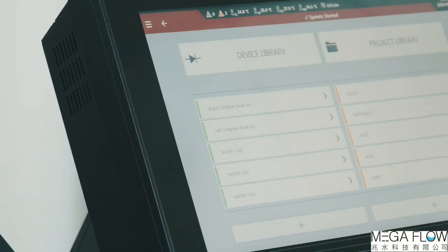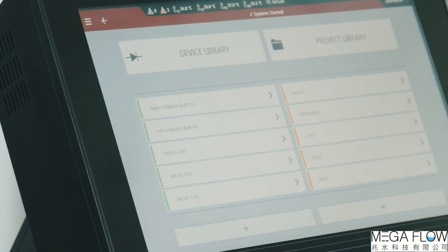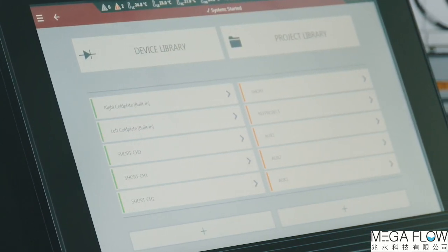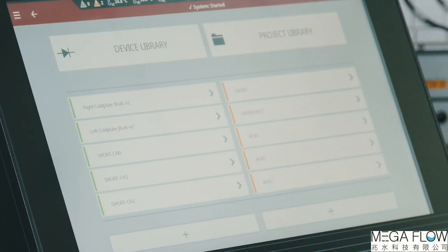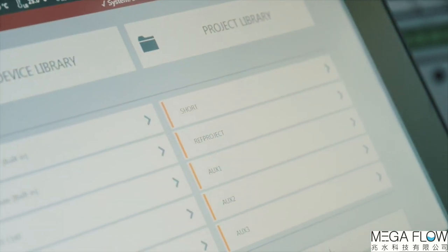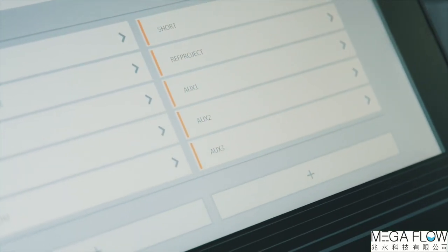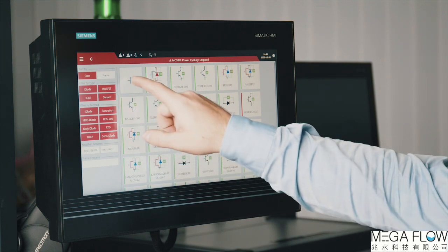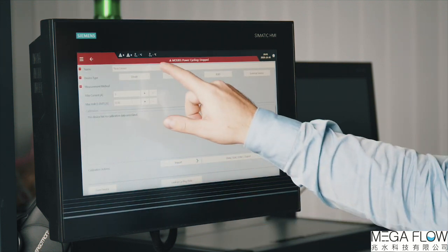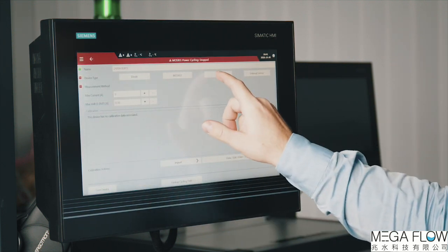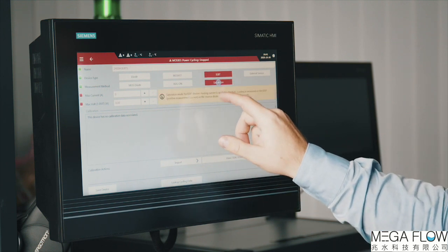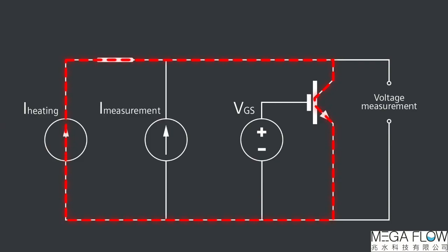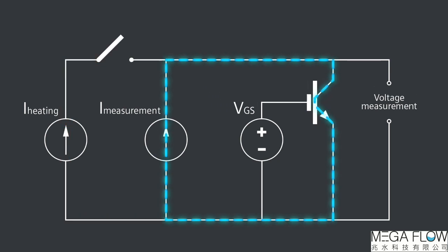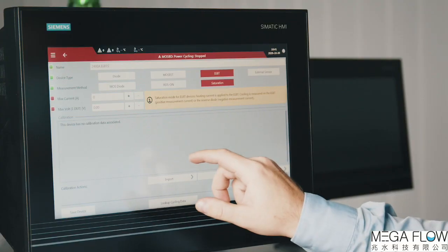The test setup is organized at 2 levels, devices and projects. Device definitions contain the most important parameters of the test samples, while the projects define the arrangement of these devices and the actual parameters. We need to define a new device for our sample. First, the measurement mode has to be selected. In the current example, the IGBTs are heated and measured in saturation mode with a constant gate emitter voltage applied to turn on the devices.